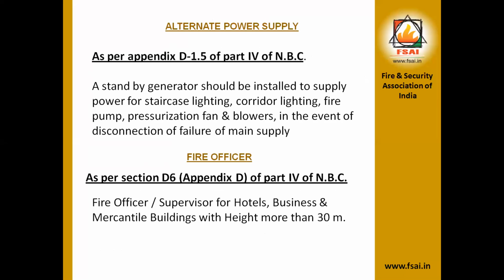A standby generator should be installed to supply power for staircase lighting, corridor lighting, fire pump, pressurization fan, and blowers in the event of disconnection or failure of the main supply. And the next is the requirement of fire officer. What should be the number of fire officers? It should be noted in the NBC code. Fire officer, supervisor for hotels, business and mercantile buildings with a height more than 30 meters. If the height of the building is 30 meters, we should provide one fire officer.